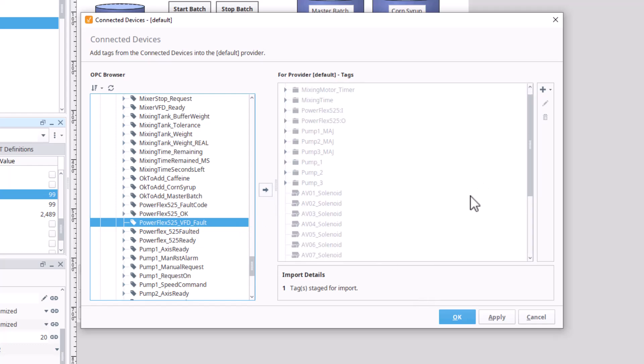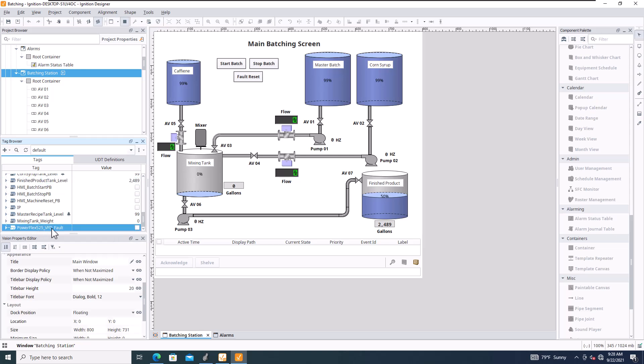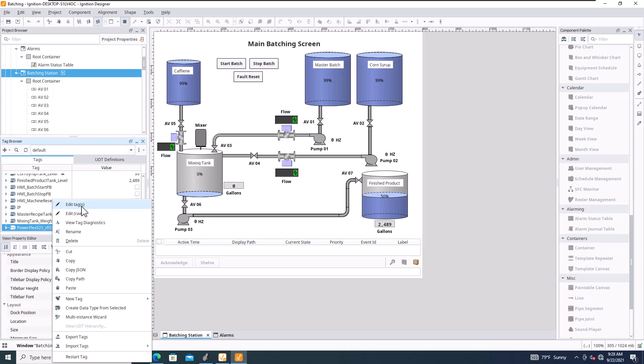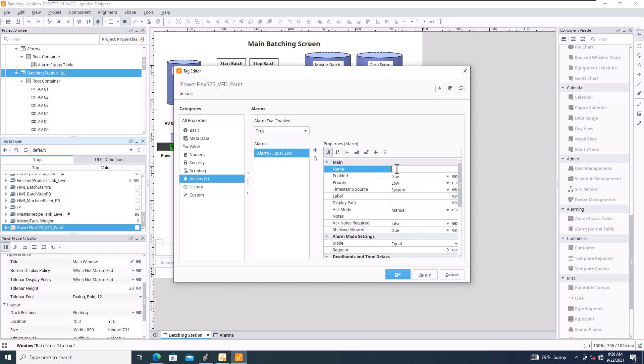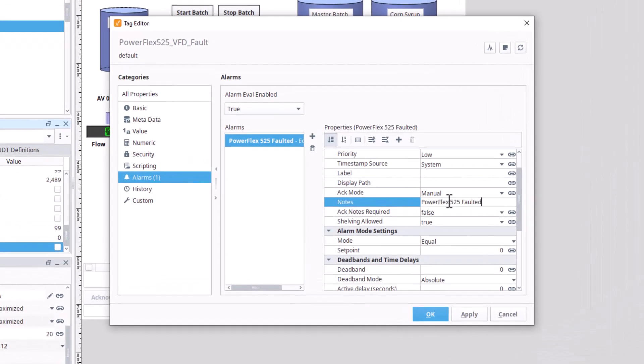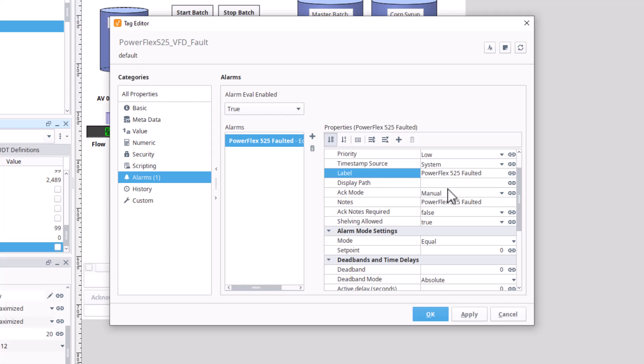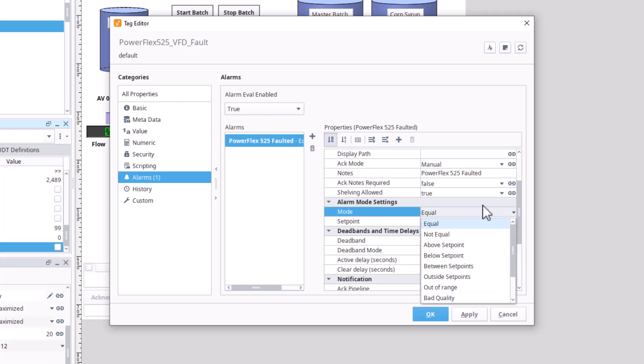Now let's come over to that PowerFlex fault tag and add an alarm. Right-click → add new alarm. Name it 'PowerFlex 525 Faulted.' Add some notes and a label. For the alarm mode, set it to 'Equal To' with a setpoint of 1 — for a binary tag, if it's equal to 1 the alarm is active.